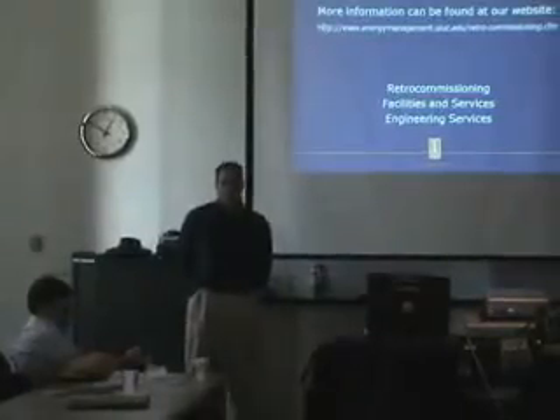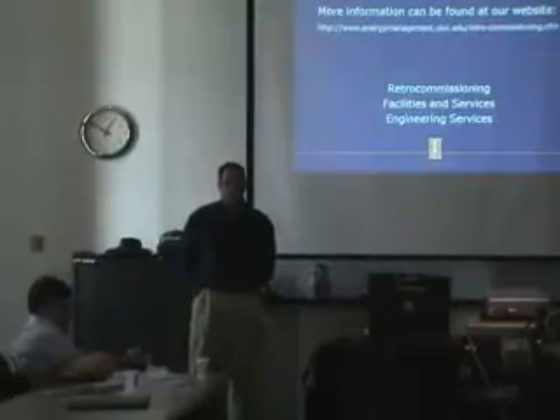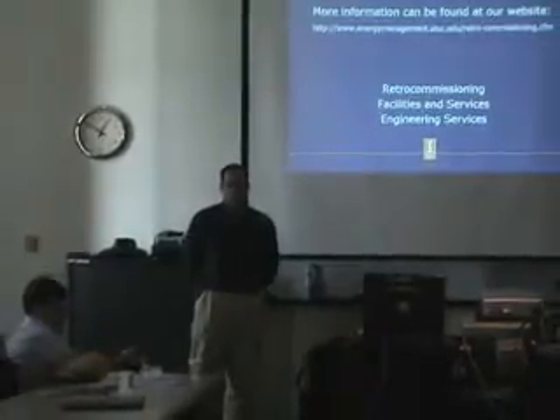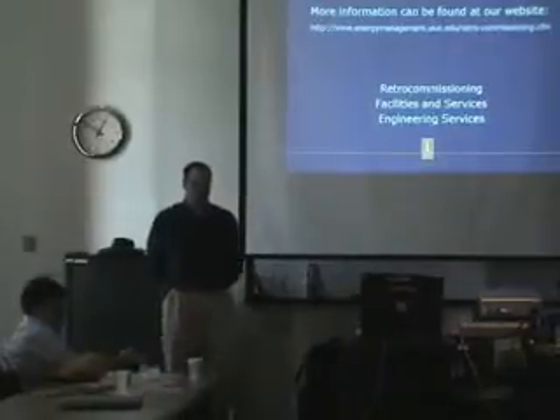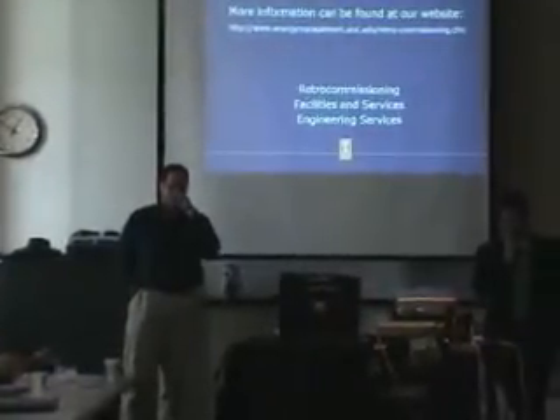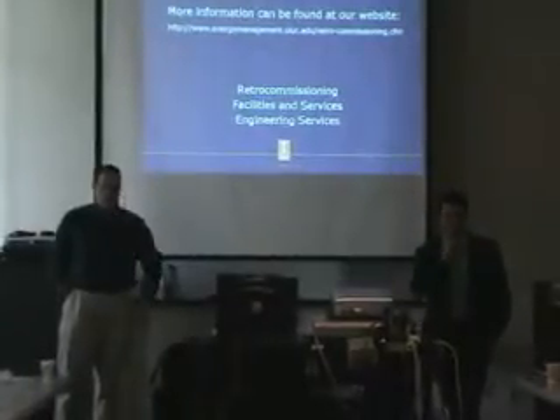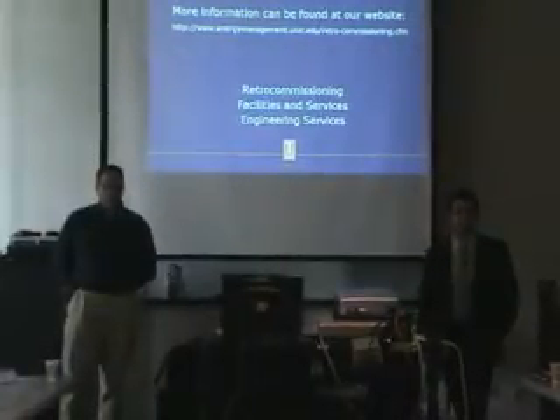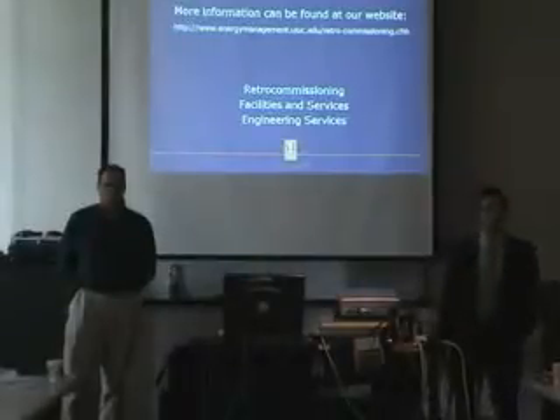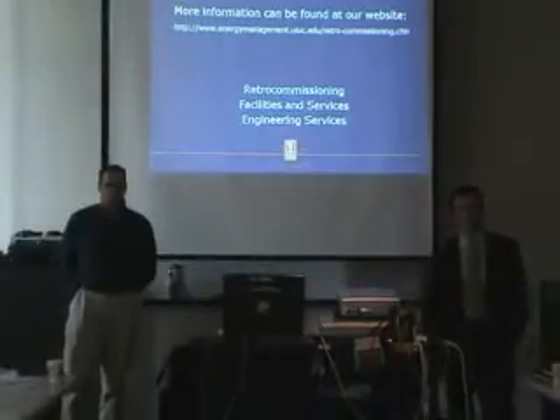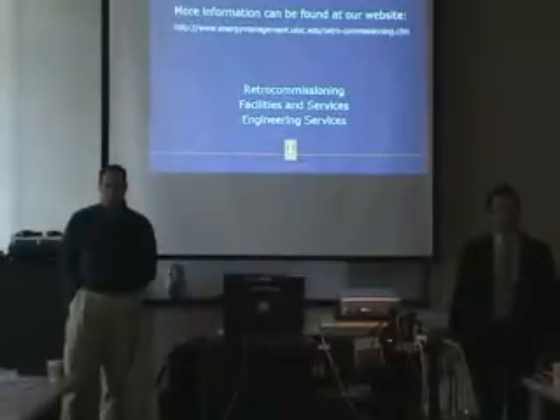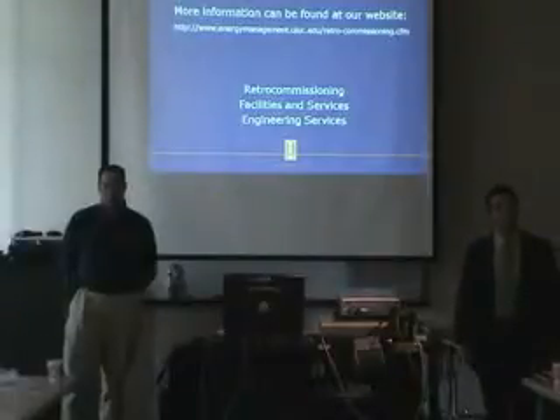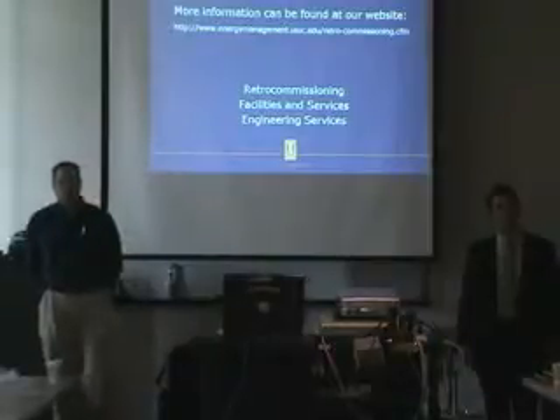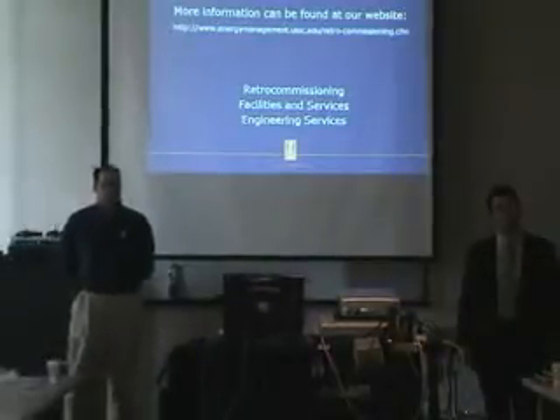Is that using utility meter data? We're using the DDC data, not a top-down approach. The one I'm thinking of uses granular temperature, pressure, right down at the IO and set point level, looking at control loops and determining when things are going out of calibration or starting to go south, letting the computer flag it as the problem grows, saying there's an issue you should check out. Sometimes you can document savings, sometimes not, but I can talk to you offline about it.